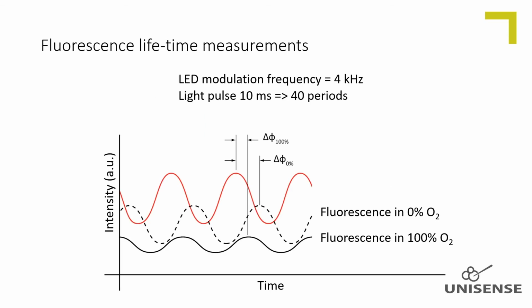The optode meter emits modulated light with a 4 kHz frequency with a 10 milliseconds pulse duration. The optode meter therefore receives a modulated light response from the fluorescing dye with the same frequency, but now with an oxygen-dependent delay, the so-called phase shift. The phase shift is used as the uncalibrated values seen in the Unisense software named delta phi with the unit degree. This is a mathematical expression of this phase shift.